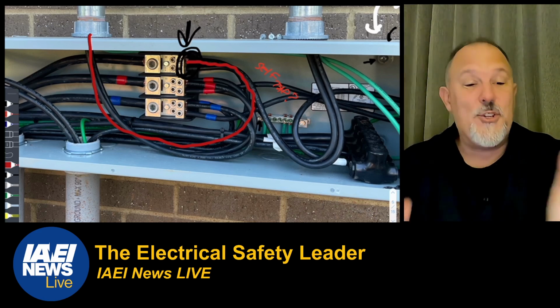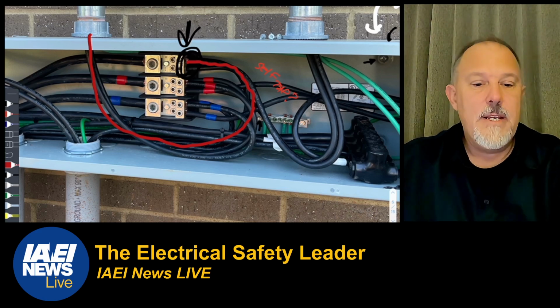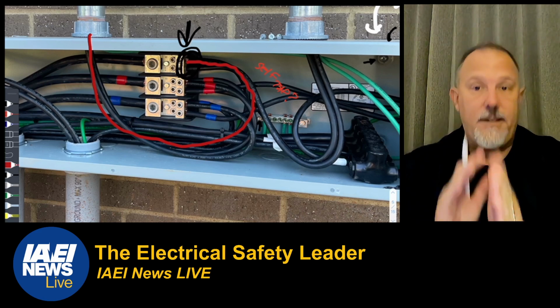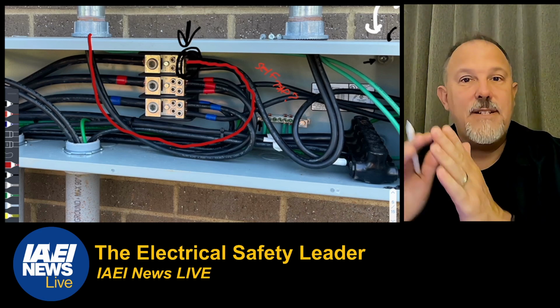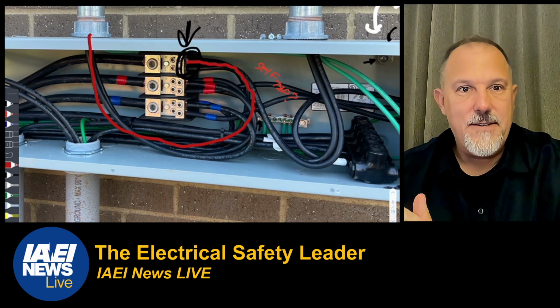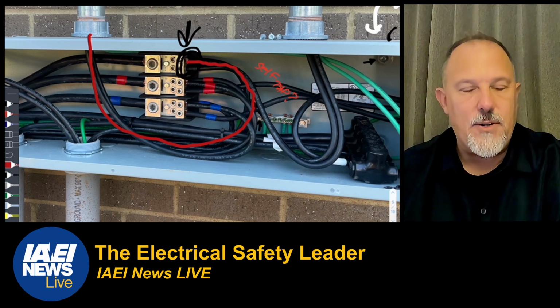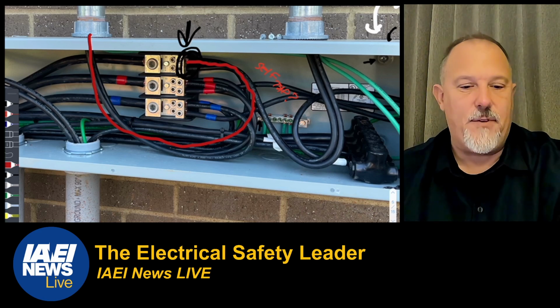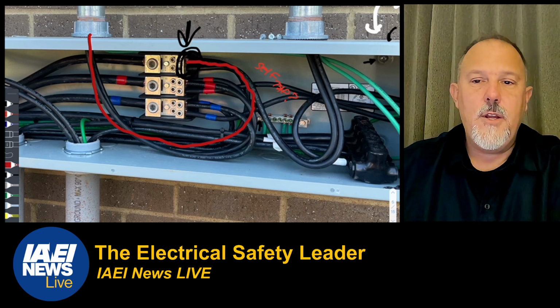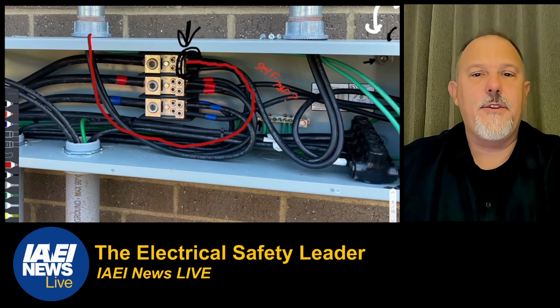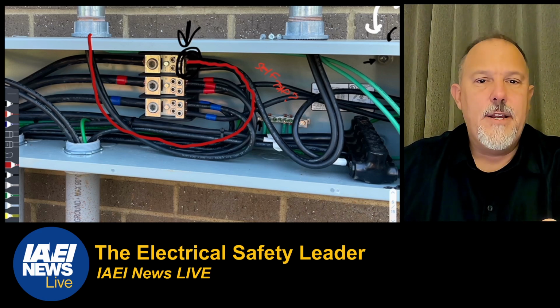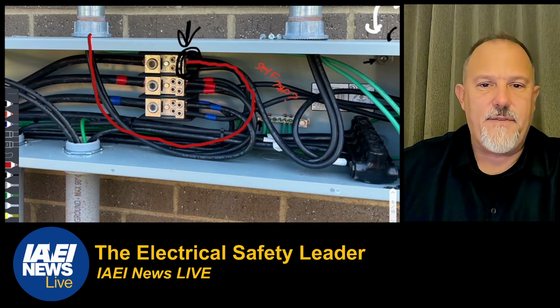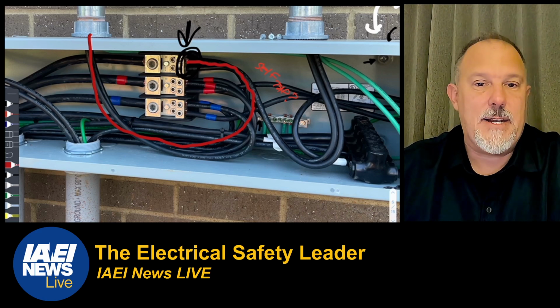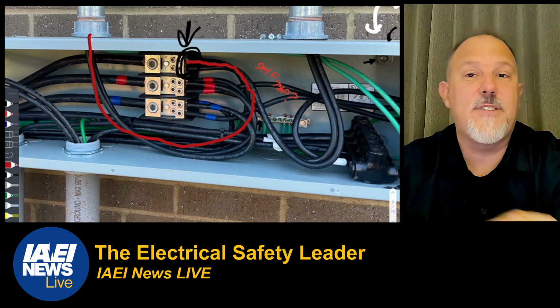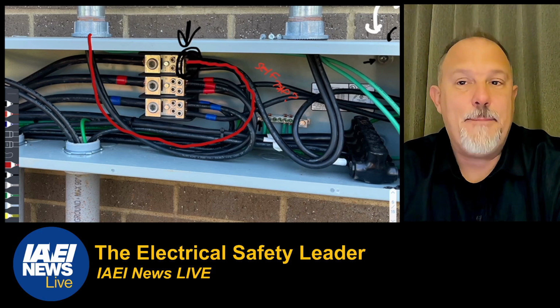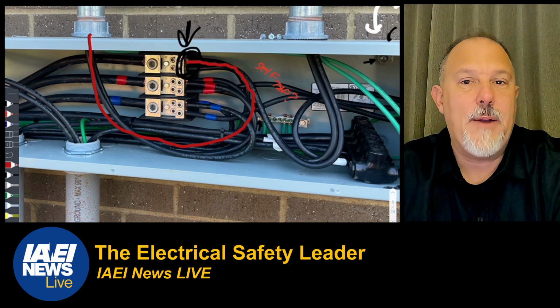The other thing you could use this for, which is cool, is to help people understand the different tap rules that are out there. And when do I have to use the 10-foot? When can I use the 25-foot? Then there's the transformer secondary, taps over 25 foot long, outside taps, unlimited length, where the conductors are located outside of a building or structure, except at the point of load termination, and comply with all of the following.